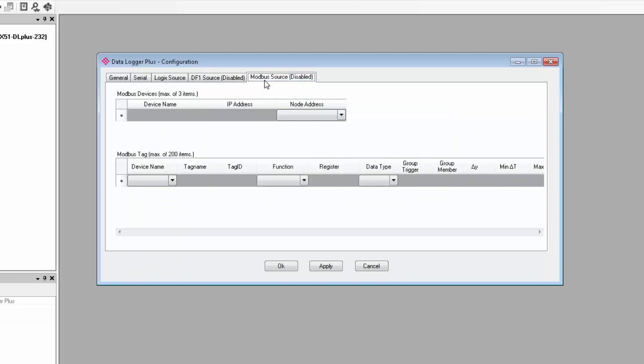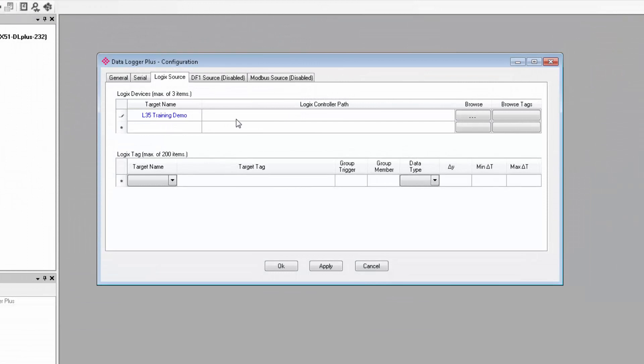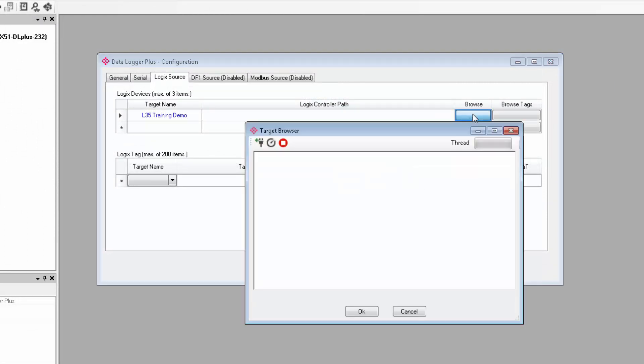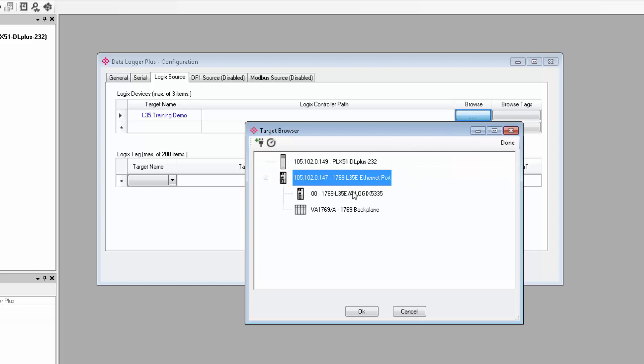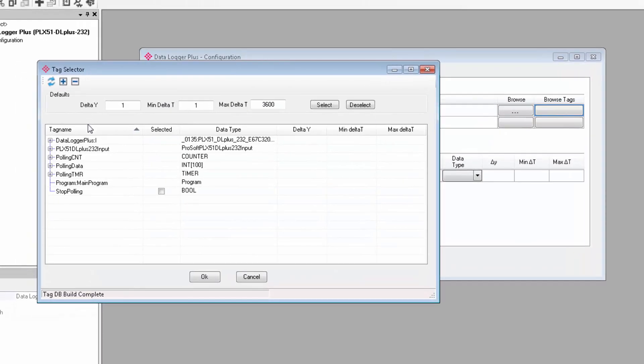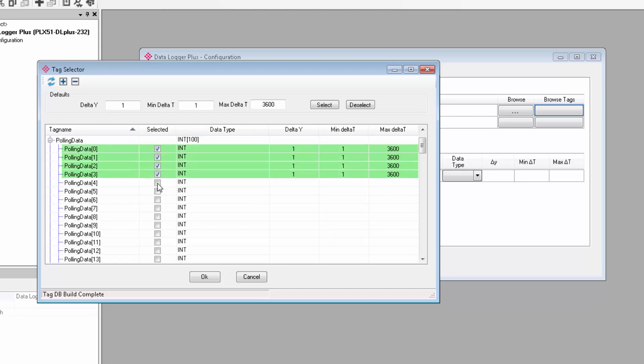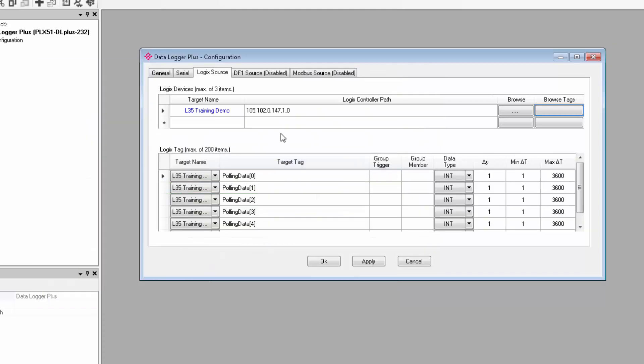The Logix Source, DF1 Source, and Modbus Source tabs are for logging data from those respective devices. I have a CompactLogix processor that I will be logging data from, so I'll configure the Logix tab. Depending on which source you choose, the other two tabs will be disabled. I'll start by giving the controller a name, something that might help me keep track of what I'm connecting to. I can then click the Browse button to browse devices on the subnet. I'll locate my controller and select my processor. The IP address, along with the slot number, will appear in the controller path field. Now I can click the Browse Tags button to pick the tags from the controller that I want to log in the PLX51. I have some tags in the CompactLogix that will change at different rates over time to illustrate the data logger's features. So I'll just check them, click Select, and then OK, and they'll appear down in the Logix Tags section.